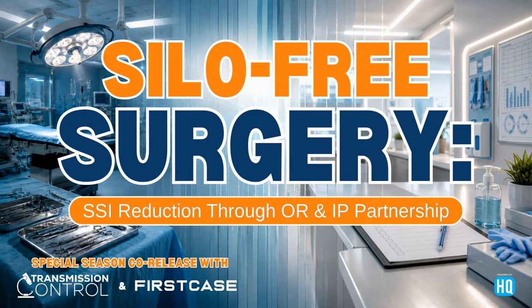Another thing was it was fast. They were going very, very fast. They're cleaning instruments extremely fast compared to what the validations do. We have 6 to clean for half the day, so we're taking our time. We're taking our due diligence to brush every single thing we can brush. So visual inspection is almost always passing for us because we have that time. In a healthcare facility, they don't have that time. They're going really fast in the processing. So those were the 2 things that we saw that are definitely discrepant between validations and real life.